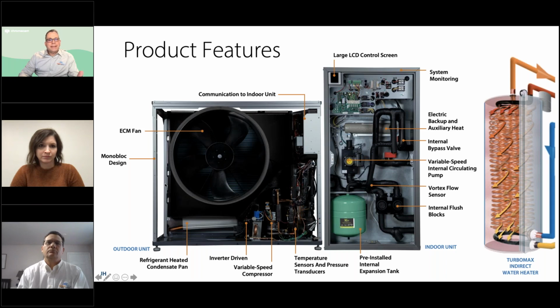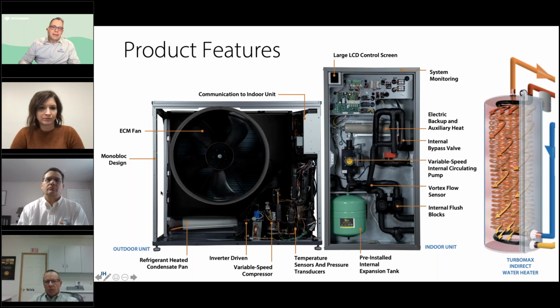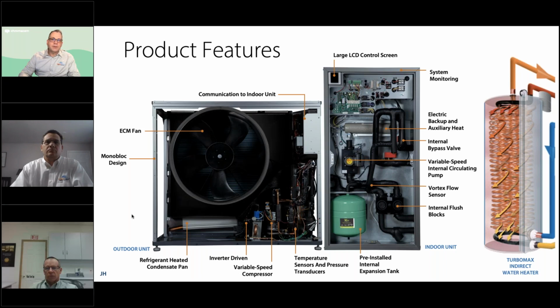So when we put all these three pieces together, the system now is really a matched system. We're not trying to source parts and pieces from various vendors and hope that they work together, because everything is communicating from indoor to outdoor. And the indoor system really is just telling the outdoor unit what it needs. I need heating, I need cooling. And then the outdoor unit takes over and handles all the defrost control. It handles switching from heating to cooling and reports back all the information to the indoor module. So that's kind of a quick overview of the components. Let's go to the next slide and look at some of the features.